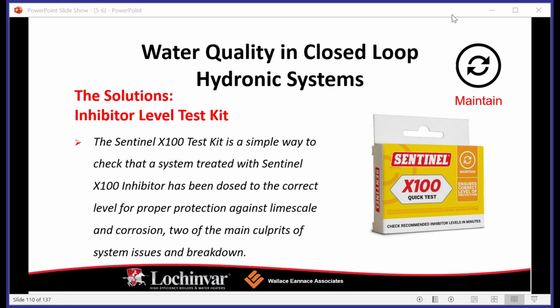So the X100 we're seeing, again, which is the rapid dose can. We do have rapid dose cans available for a lot of the Sentinel product lines. This is really super helpful, okay? So 1 can of the rapid dose inhibitor typically is good for 1 residential installation. So what you're seeing here is a can, it's pre-charged. What you're gonna do is snap that thing off, mount it to the top of the can, and screw it onto a boiler drain. You open the boiler drain, and then you crack the can, and it's actually gonna push the treatment into the system.